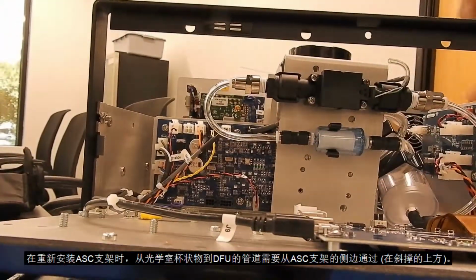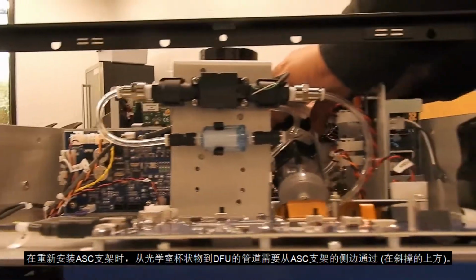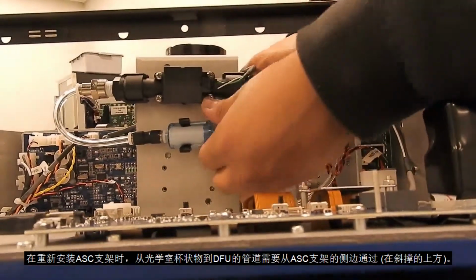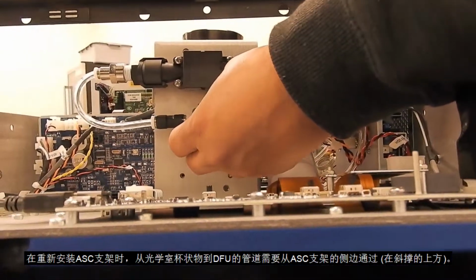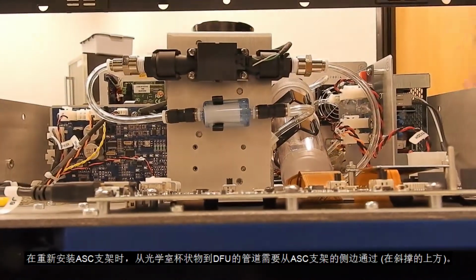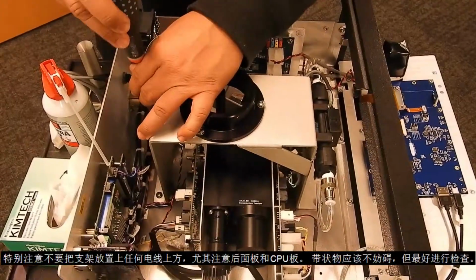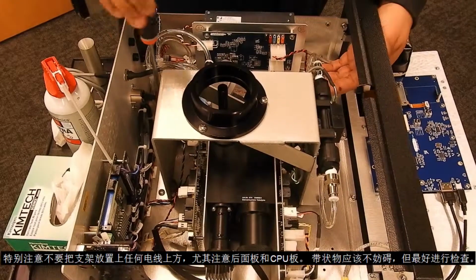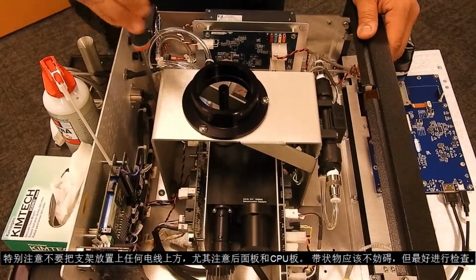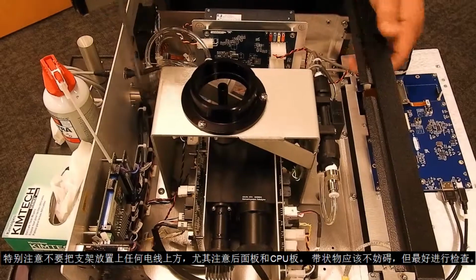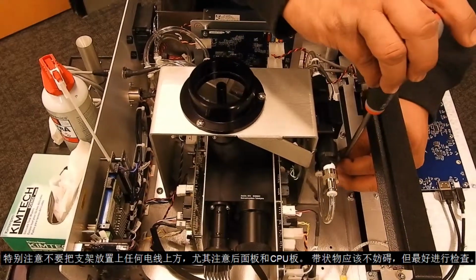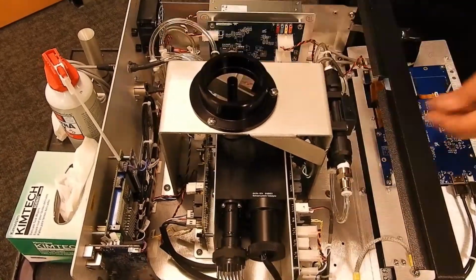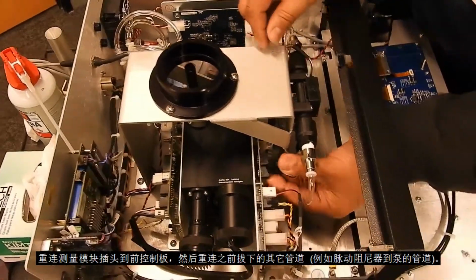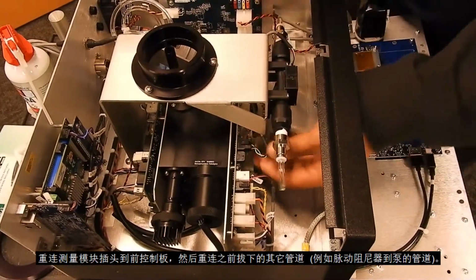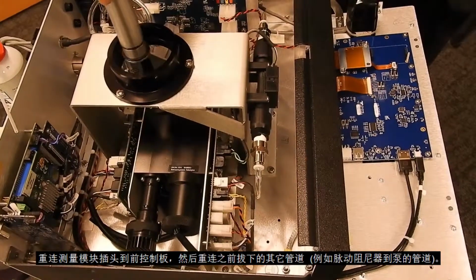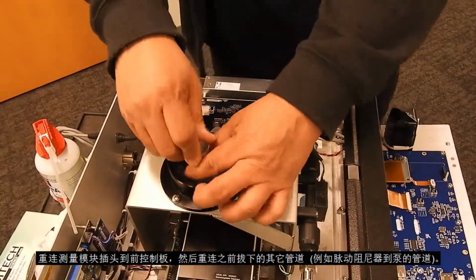When reinstalling the ASC support, the tubing from the optical cell cup to the DFU needs to be routed through the side, above the diagonal support of the ASC support. Pay special attention not to place the support on top of any wires near the rear panel and CPU board. The harness should be out of the way, but it is a good idea to check. Reconnect the measurement module plugs to the front control board, as well as any additional tubing that was unplugged, such as the pulsation dampener to the pump.